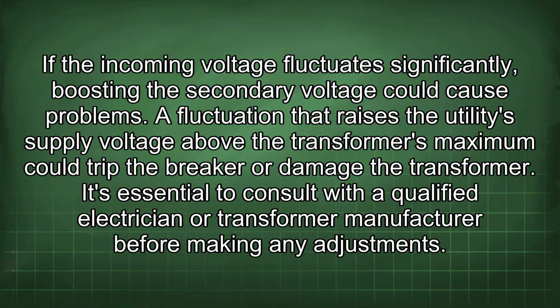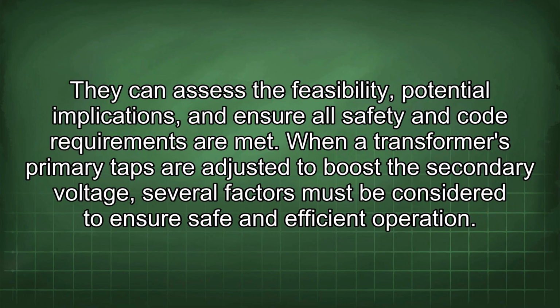If the incoming voltage fluctuates significantly, boosting the secondary voltage could cause problems. A fluctuation that raises the utility supply voltage above the transformer's maximum could trip the breaker or damage the transformer. It's essential to consult with a qualified electrician or transformer manufacturer before making any adjustments. They can assess the feasibility, potential implications, and ensure all safety and code requirements are met.